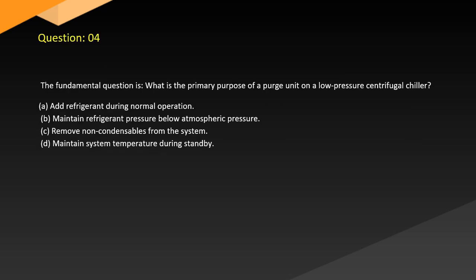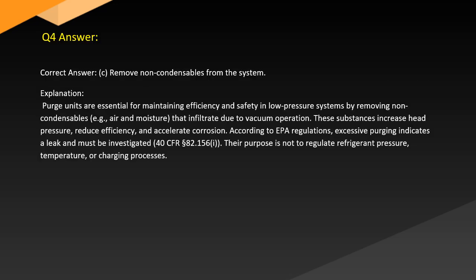Question 4. The fundamental question is, what is the primary purpose of a purge unit on a low-pressure centrifugal chiller? A. Add refrigerant during normal operation. B. Maintain refrigerant pressure below atmospheric pressure. C. Remove non-condensables from the system. D. Maintain system temperature during standby. Answer. Correct answer: C. Remove non-condensables from the system.